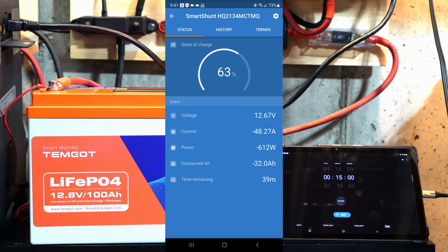Okay, that time it spiked over 219 amps for just basically a second. So clearly this battery is capable of outputting pretty high amperage, well over 200 amps, for a very short period of time to allow you to handle some very high current spikes for startups like compressors and things like that. But it definitely performs up to that 100 amp continuous spec and that 1,280 watt spec.